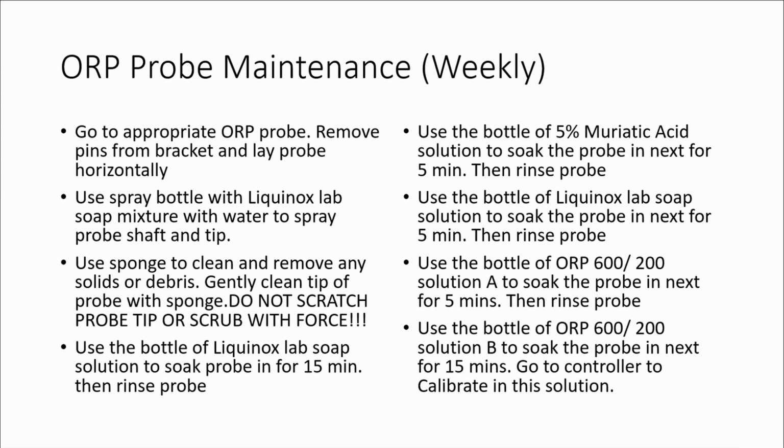Of course, the probes are plus or minus 50, so you should be 550 to 650. I mean, they're usually within 20 of that, give or take. And then you just calibrate it, and the next week it's usually right in that same range.